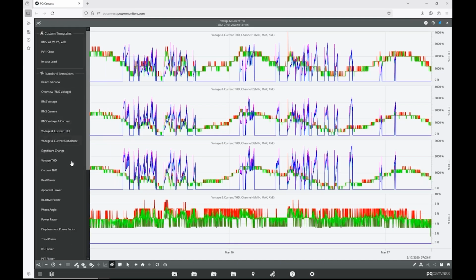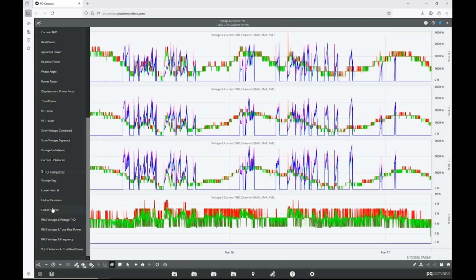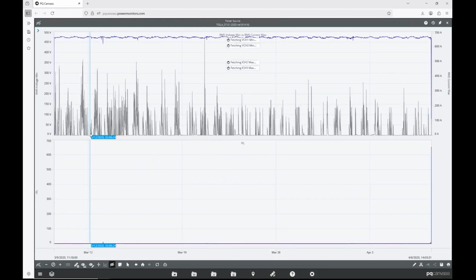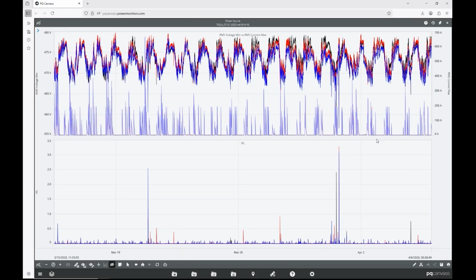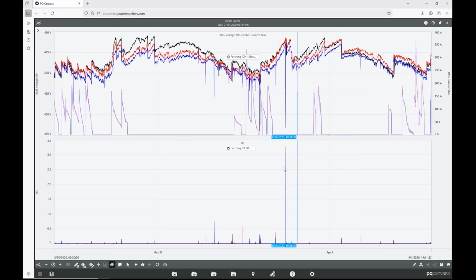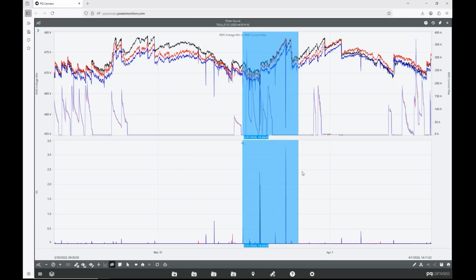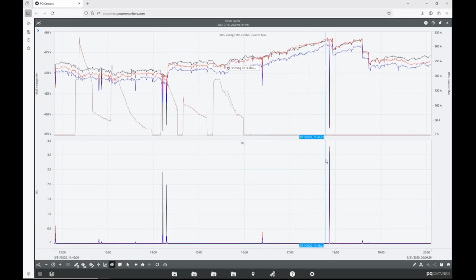If we take a look at flicker source. So now we're looking at voltage minimums, current maximums, and instantaneous flicker level here in the bottom to see if a flicker is being caused by this, by the load. And if it is, how bad is it? So here's the instantaneous flicker. It's fairly low during the whole recording, except for a few excursions where we're going over 2 for IFL.